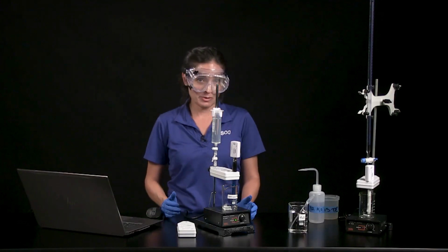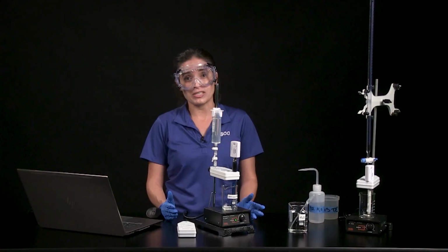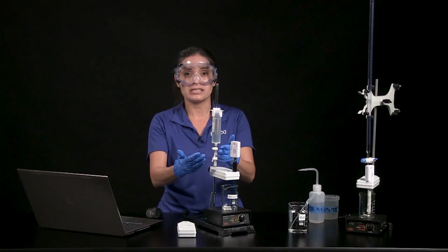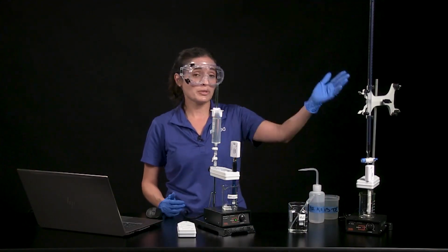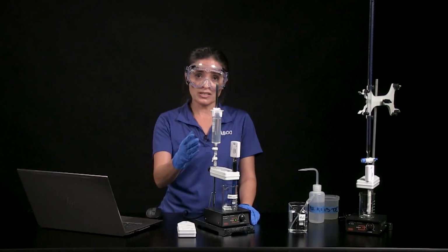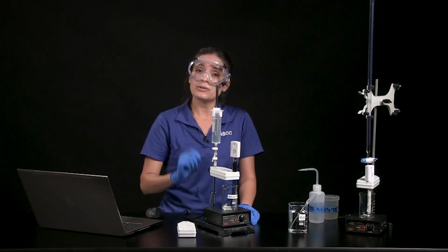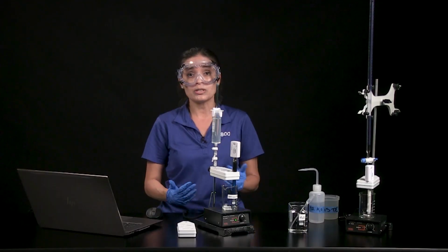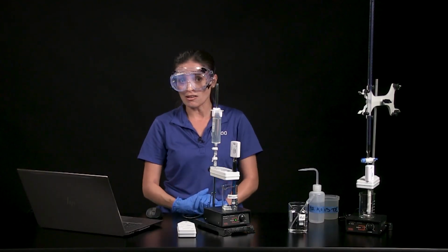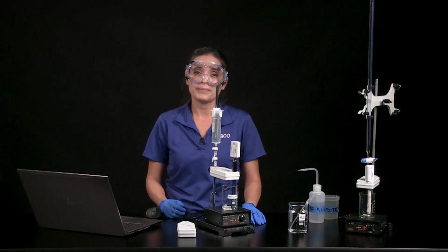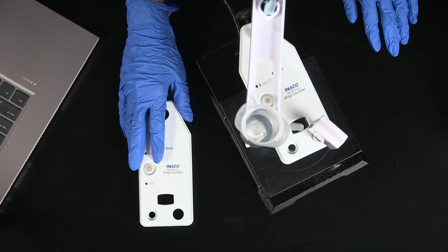The drop counter comes pre-calibrated for water-based solutions delivered by the drop dispenser system. If you are using a traditional burette, or your water-based titrant concentration is significantly greater than 0.1 molar, or you're using something other than water as a solvent, you should calibrate the drop counter. The sensor stores the last calibration.